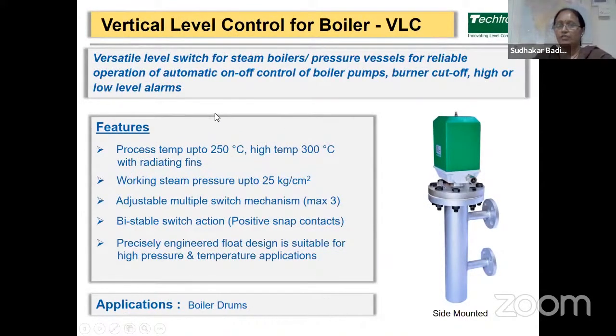This is a versatile switch used in steam boilers or pressure vessels for reliable operations of automatic on-off control of boiler pumps, burner cutoffs, high or low level alarms. It can be used up to a temperature of 250 degrees Celsius, and high temperature is available up to 300 degrees Celsius with radiating fins. Working steam pressure is up to 25 kg per centimeter square. It has a 3 adjustable switching mechanism, that is air brake switches. This switching action is a bistable switch action. These precisely engineered float designs are suitable for high pressure and high temperature applications. This is generally used in boiler drums.